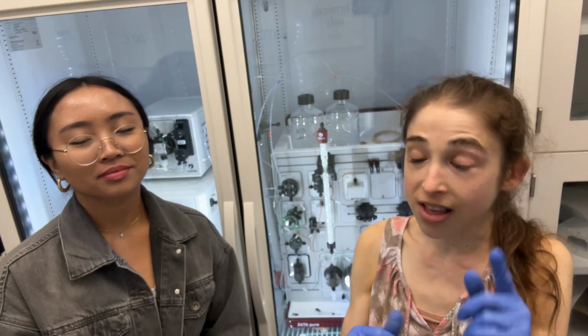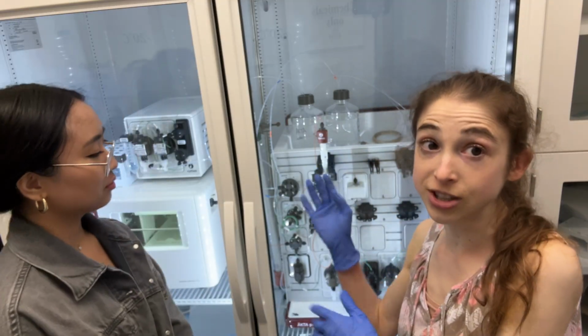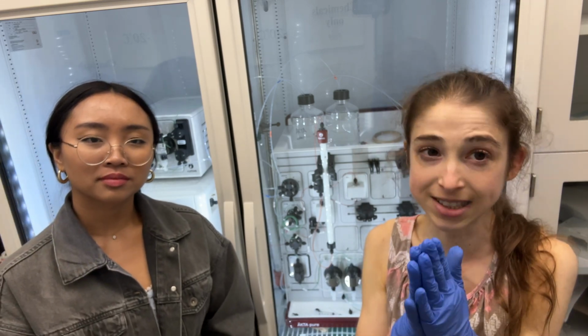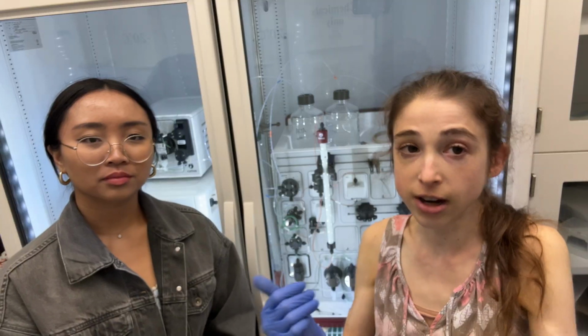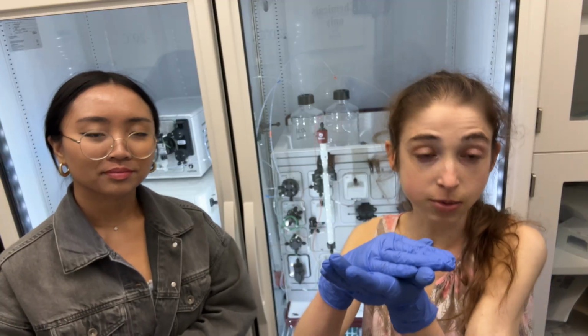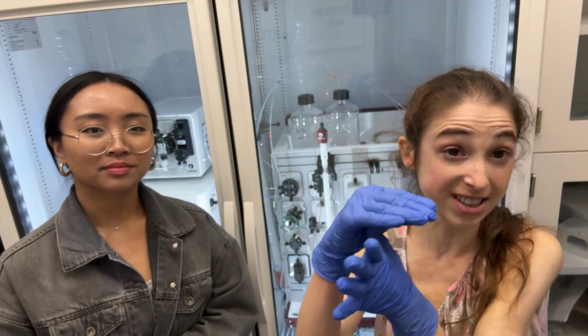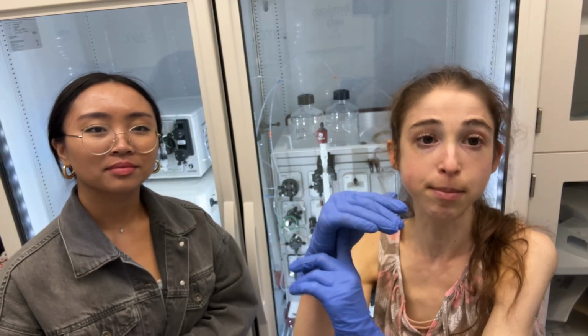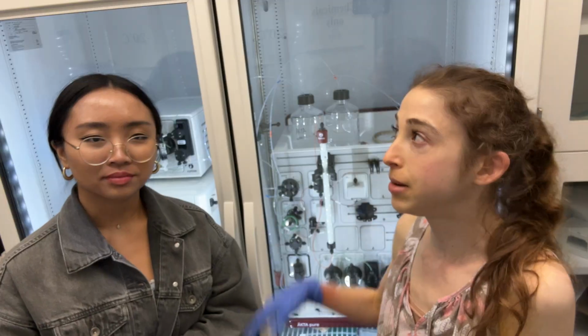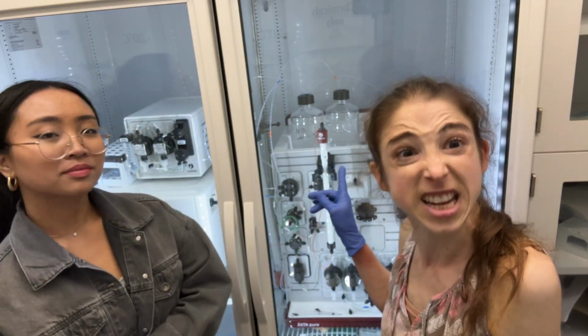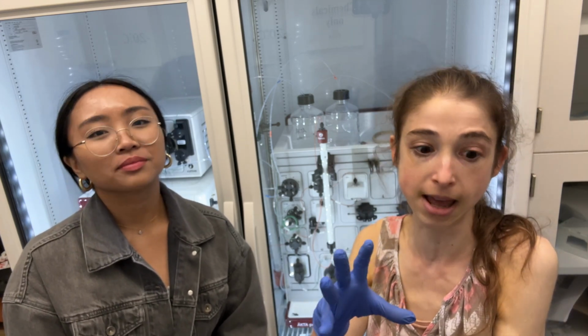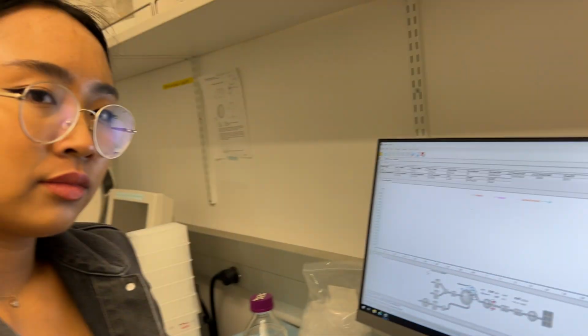One thing though, is that ethanol at low temperatures, so we have our ÄKTA in the fridge, and at low temperatures especially, ethanol is going to be more viscous. So you gotta lower the flow rate. And so what we actually did is we set up a method in our UNICORN where we have it set to monitor the pressure. So we don't just have a pressure limit, but like a pressure sensor based on the column type. But you also, if possible, can limit the flow rate so that you set a flow rate, but it'll go slower to avoid going over that pressure, because you don't want to mess up your columns. You don't want to get salt precipitating in them, and you don't want to over-pressurize them. So Karina's going to show how we can set up a method to do our wash for us.